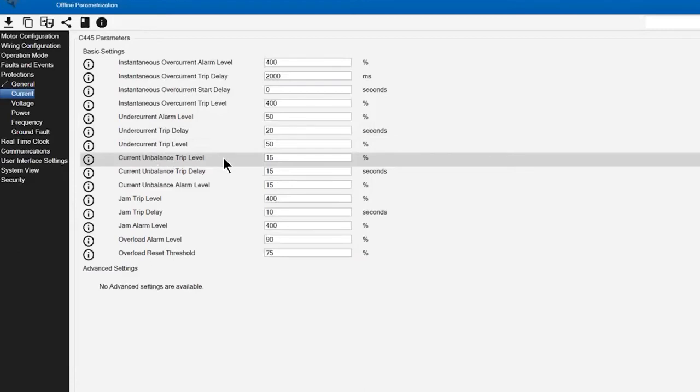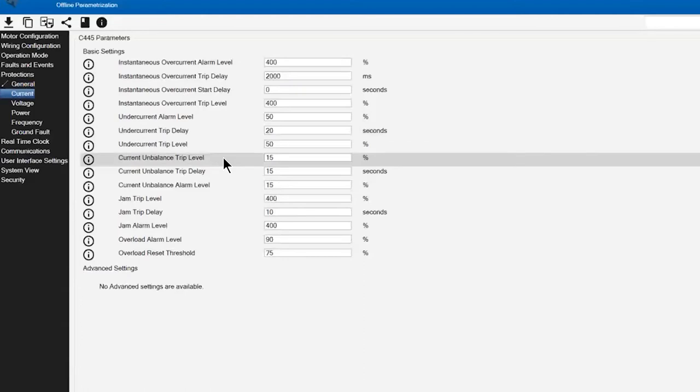As I have displayed here, any electrical failure within a motor—such as a winding failure, bad or loose connection—will be expressed in the current imbalance while the motor is running. Having an early insight into that could save a multitude of motor failures in the field.